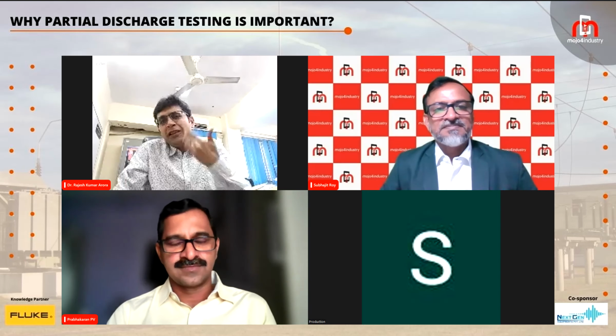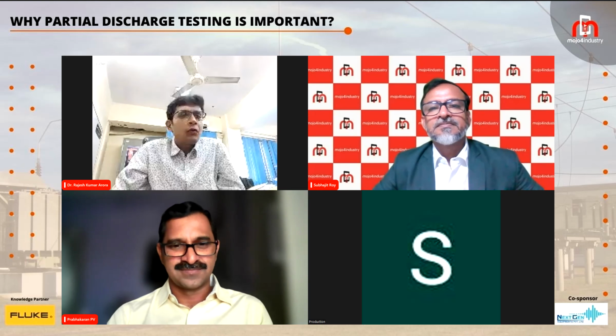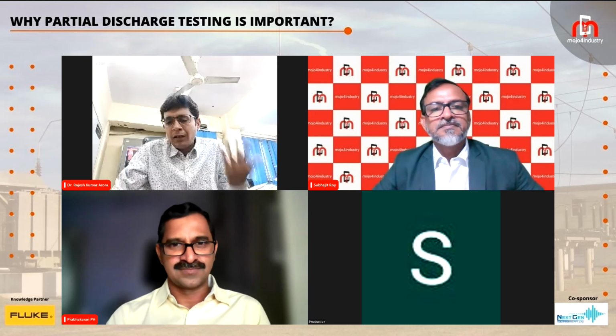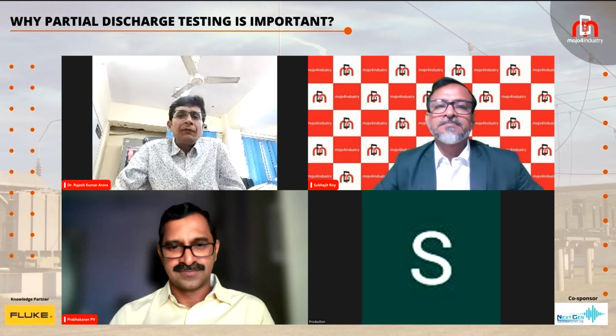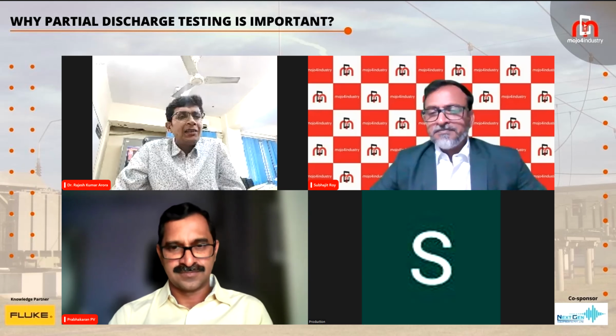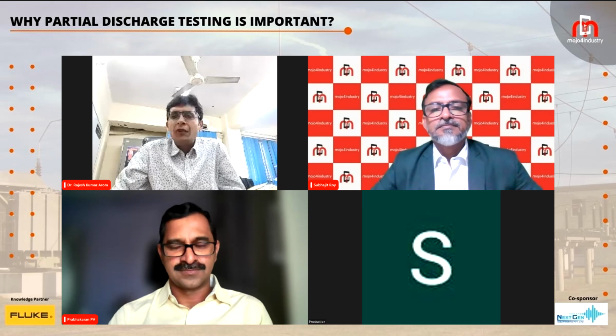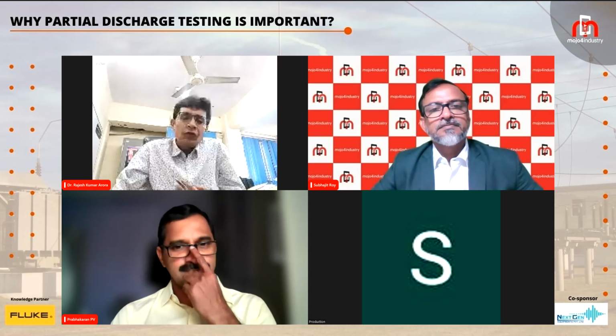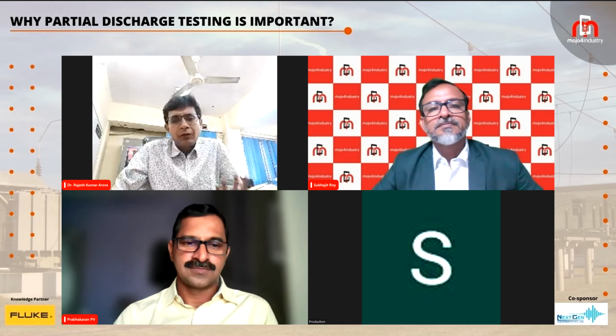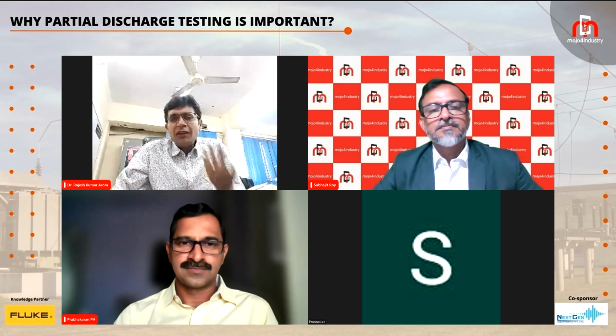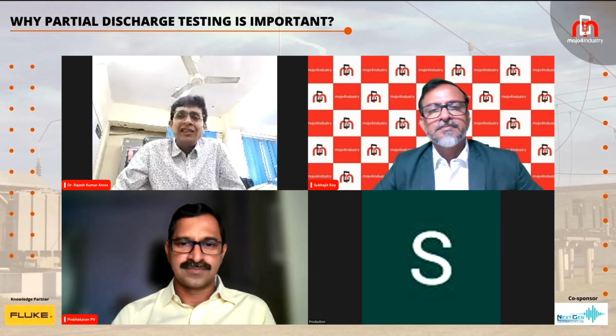It is important. Now coming to IEC and IS standards, there is IEC 60270 for the conventional method. There are also some CIGRE documents: 366, 662, 654. You can go through those. All these are relevant documents which govern partial discharge measurement and its requirements.